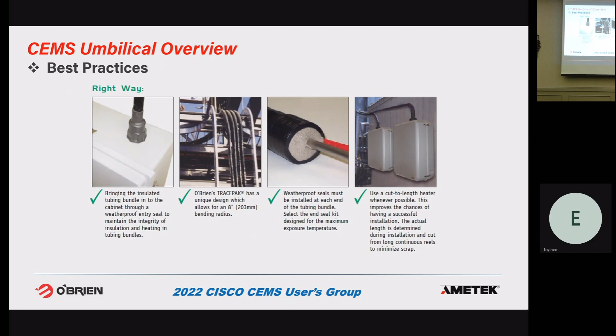So, troubleshooting. I do most of the troubleshooting, and I've been doing it for 15 years. This is my highlight of all the troubleshooting I've done over the years. This was a line that had 2 tracers inside. It was too long for a single circuit, so it was 2 tracers end to end. We'd put in the midpoint terminations, run extra wires to the end, and connect to the tracer at the far end. So you had 2 heating circuits.